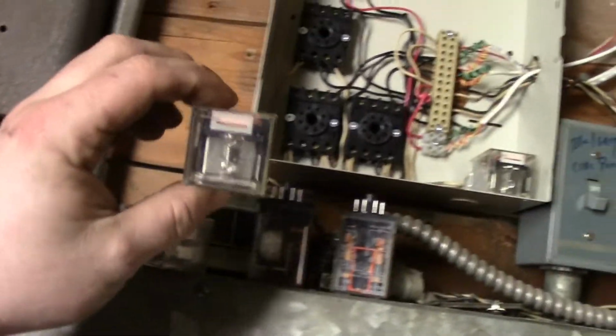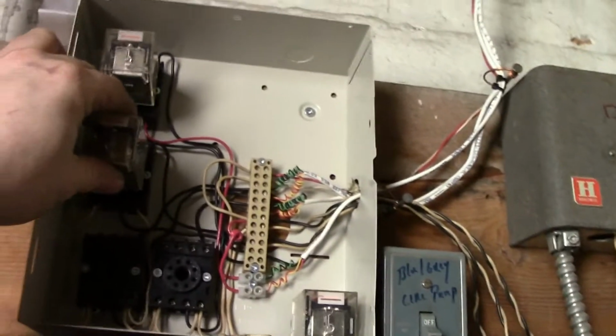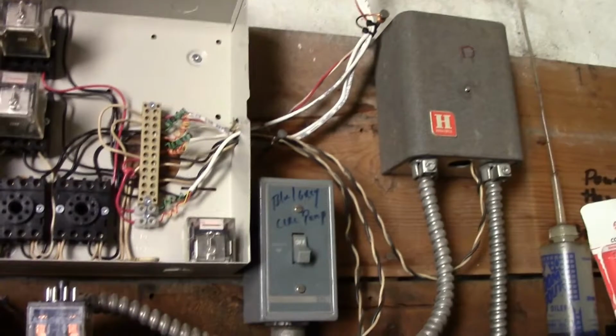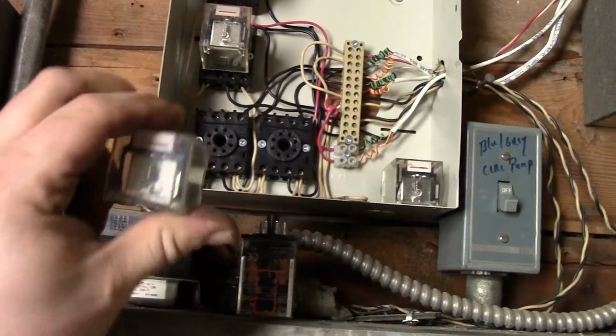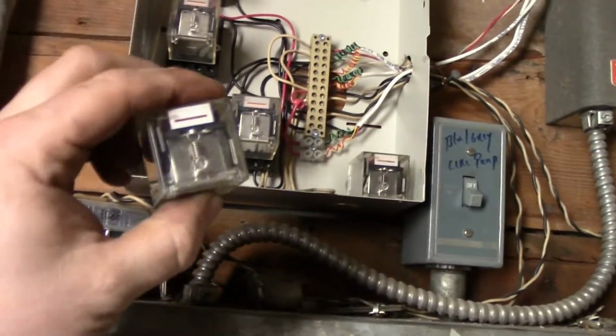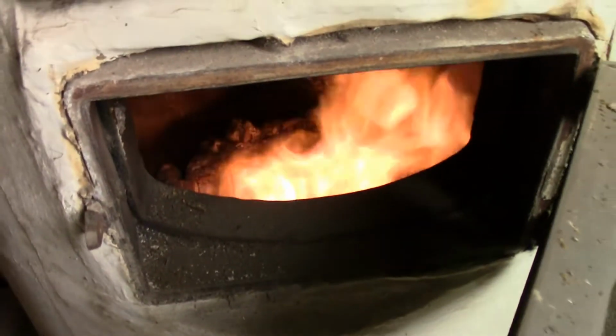by the way, all these relays are the exact same. So, high temperature relay, and of course it's not calling. The recirculator, and that clicked. So, that's off and going. All right, now the two boilers. And so, you go there, and that's one. And that's two. Turn you back on, and we'll just quickly verify. Oh yeah, you look good and happy. Yep, you look good too.